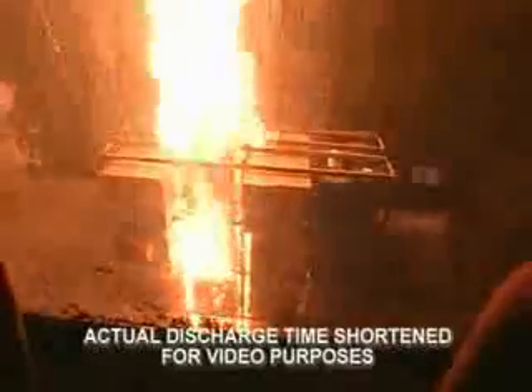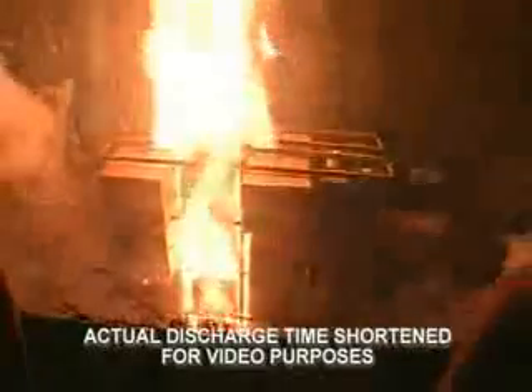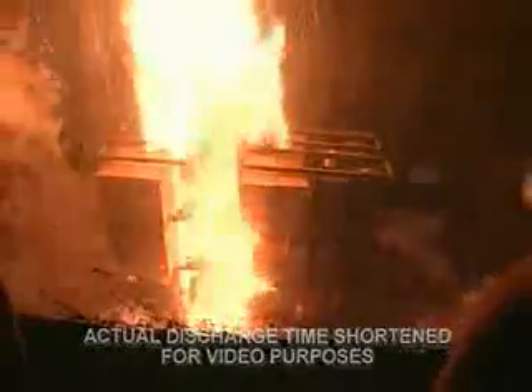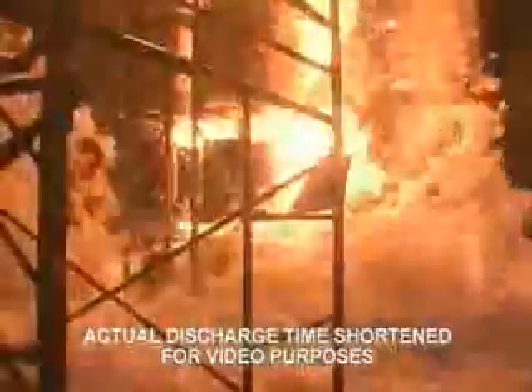A few seconds after the system actuated, the foam generators began to discharge high-expansion foam. Notice how this dangerous running spill is immediately contained from spreading. Within 15 seconds, the foam blanket has reached the involved area.